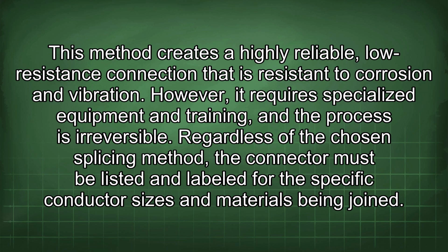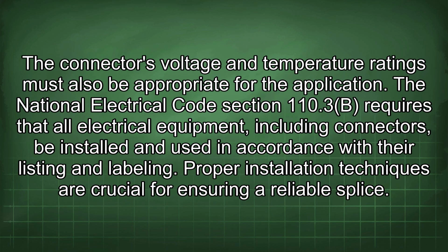Regardless of the chosen splicing method, the connector must be listed and labeled for the specific conductor sizes and materials being joined. The connector's voltage and temperature ratings must also be appropriate for the application. The National Electrical Code Section 110.3(B) requires that all electrical equipment, including connectors, be installed and used in accordance with their listing and labeling. Proper installation techniques are crucial for ensuring a reliable splice.